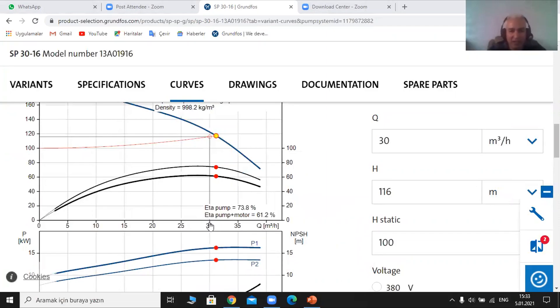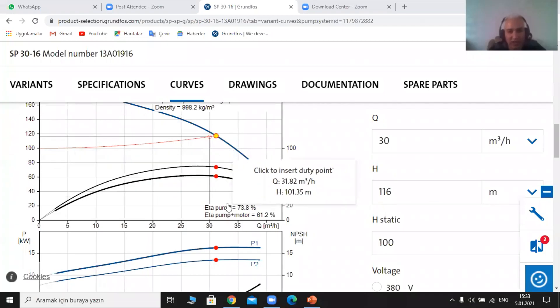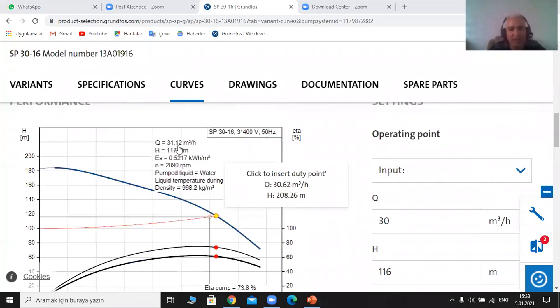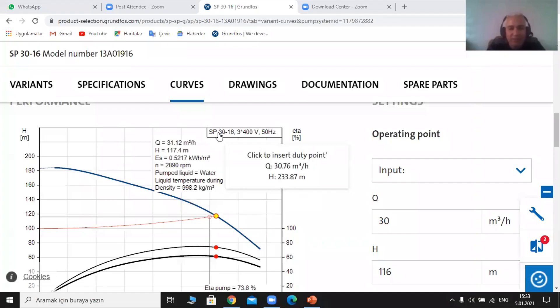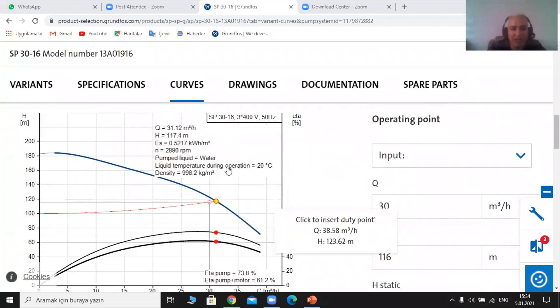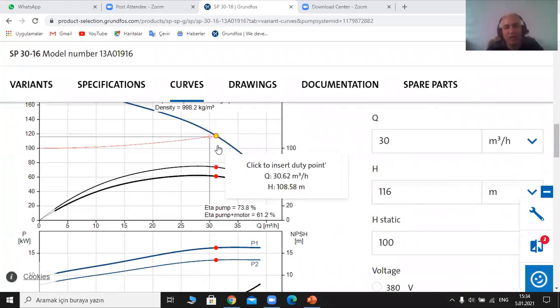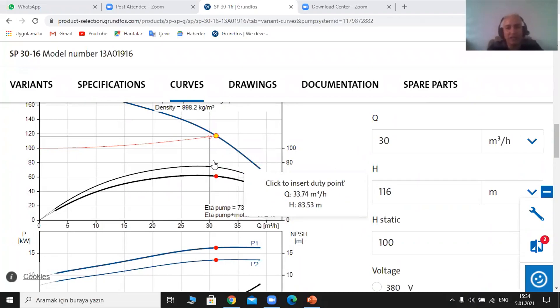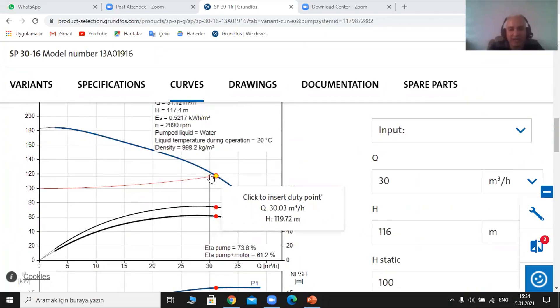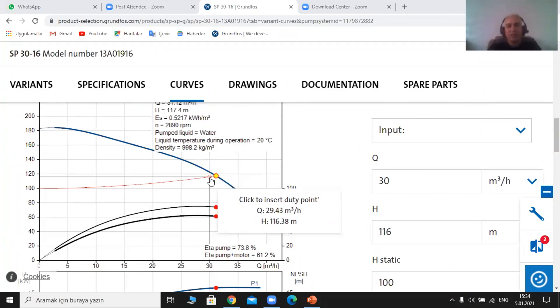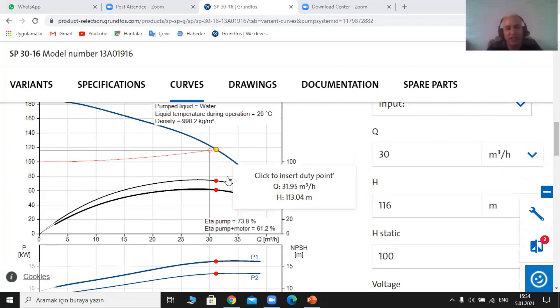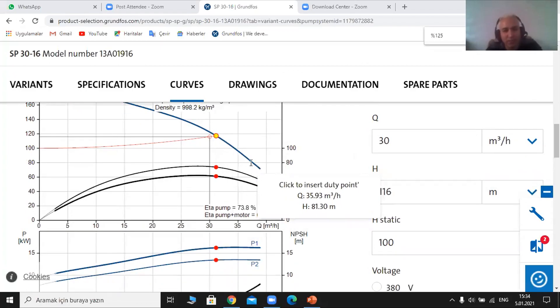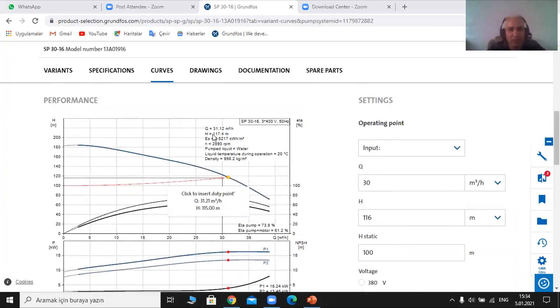The system curve is based on the duty point and the static head, and it goes along until it crosses with the pump curve. The pump flow rate I asked for was 30 by 116 — this is my duty point. But actually, the flow rate is 31.12 and the head is 117.4. This happens because I chose the pump somewhat far in range, or I may have the duty point chosen incorrectly — maybe I have lots of losses, or the static loss I thought was 100 is actually 90, so I have a 10-meter difference, making the curve totally different.